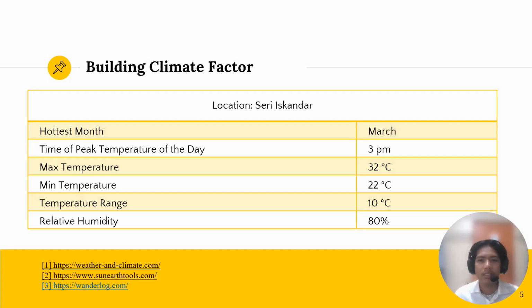So this is the building climate factor. Since the mosque is located in Seri Iskandar, we take all the related information for this location. We have the hottest month, which is in March, and the peak temperature of the day is at 3 p.m. So we have a temperature range of 10 degrees Celsius, ranging from 32 degrees Celsius until 22 degrees Celsius, and it has a relative humidity of 80%.